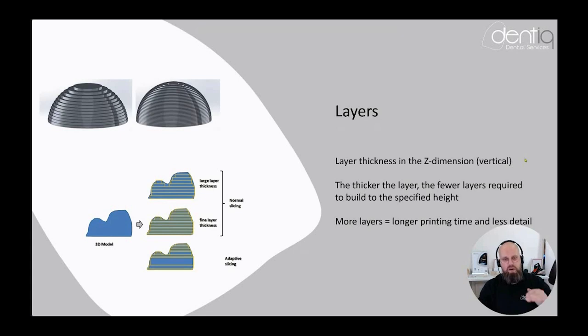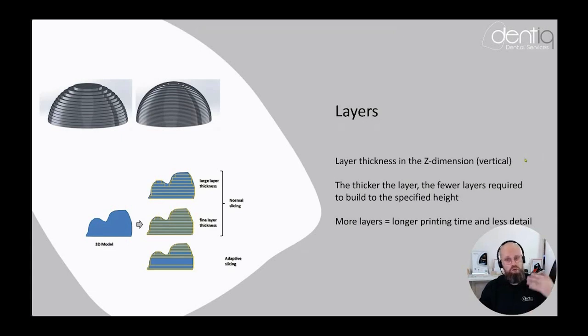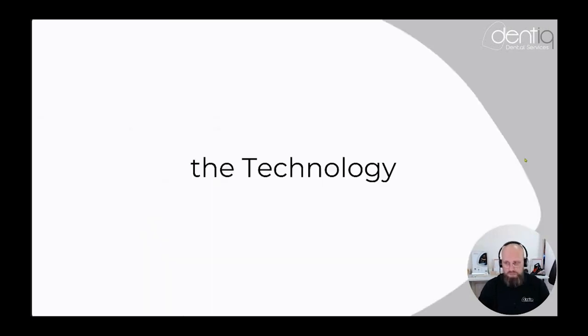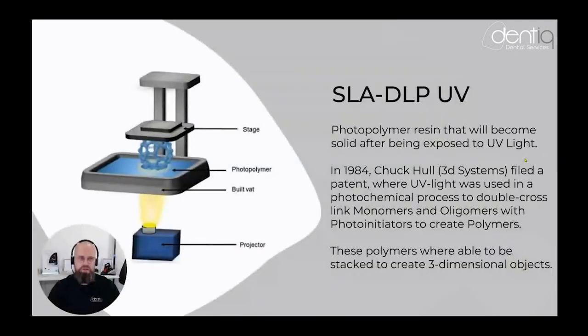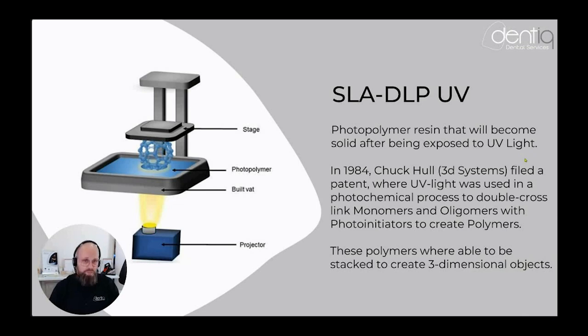So the basics of 3D printing: layer upon layer to build an object. Finer layers give more smoothness and detail but increase print time. In dental, we primarily use SLA or DLP UV technology. We have a resin tank filled with photopolymer resin — particles that react to UV light and solidify on contact. Pigmentation particles within the resin provide the color.